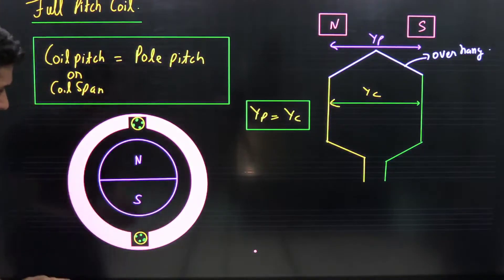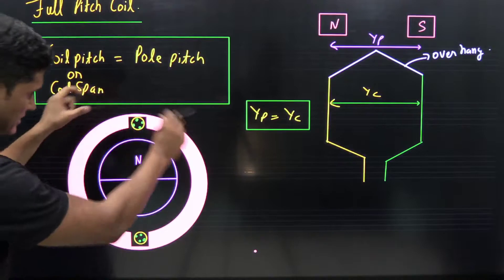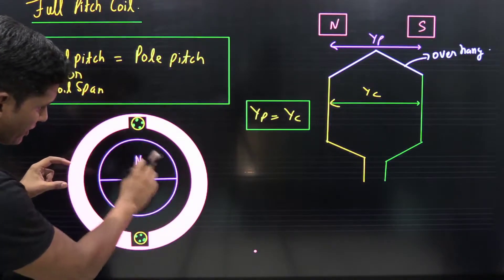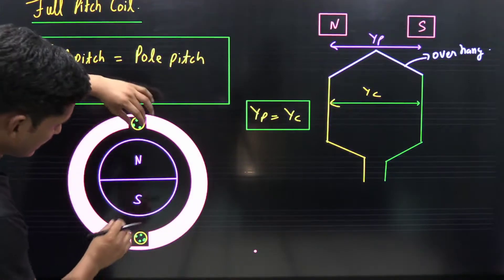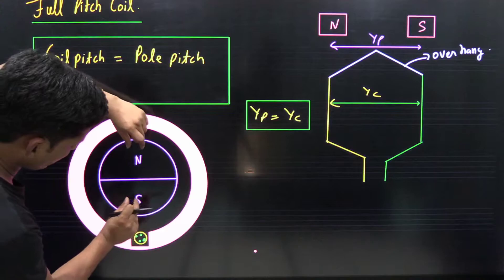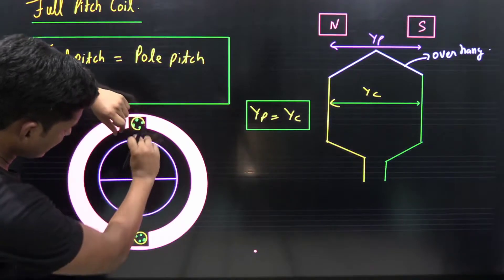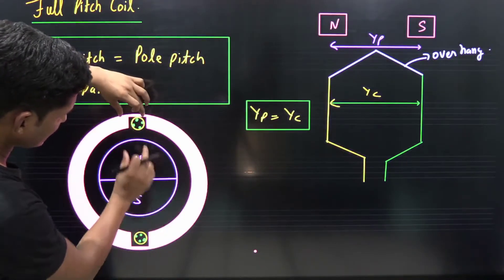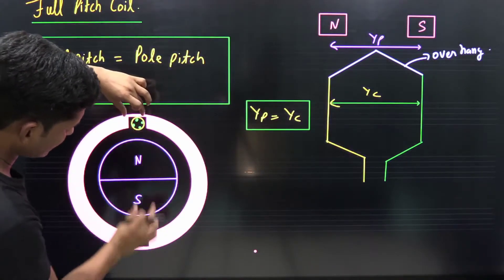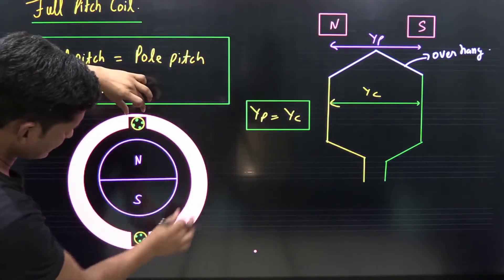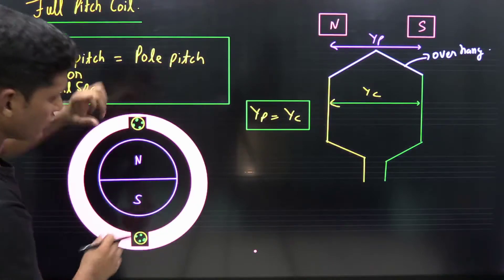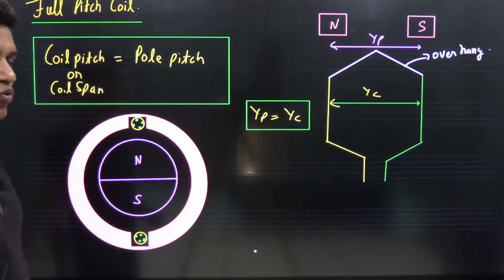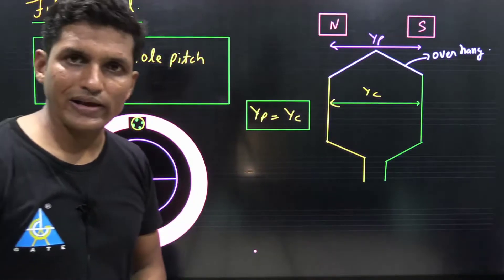In this particular example, there is a stator and a rotor, and a field winding is placed on the rotor. The distance between north and south pole is YP, whereas the distance between the two coil sides is YC. Here YC is equal to YP, and it is known as a full pitch coil.